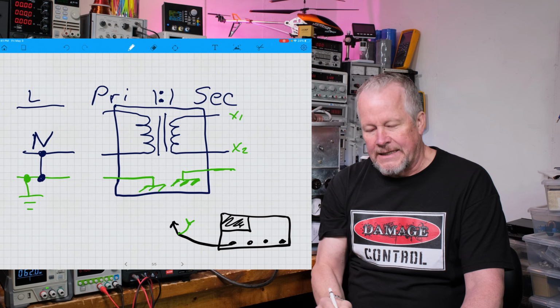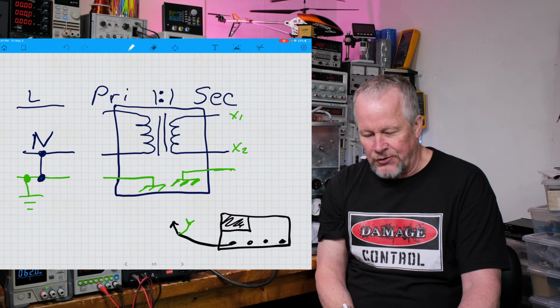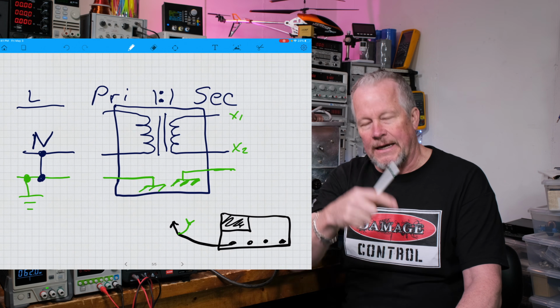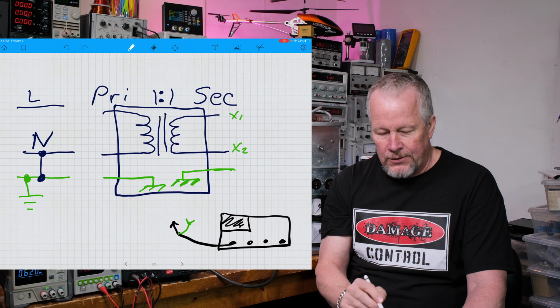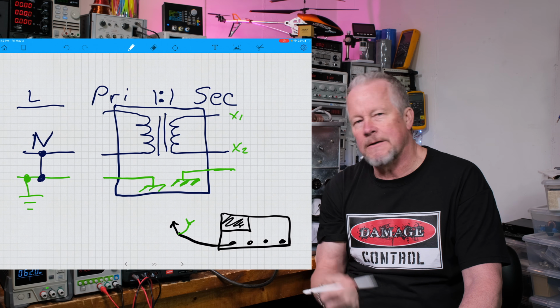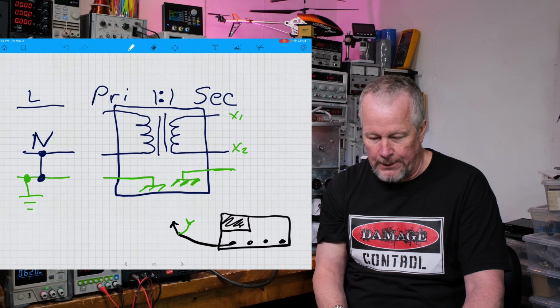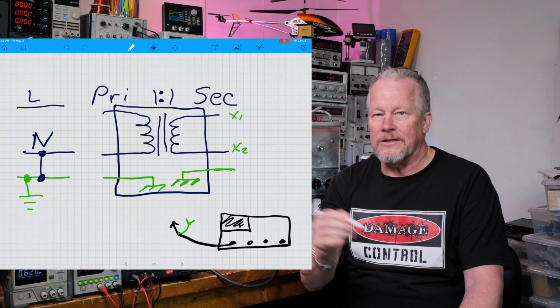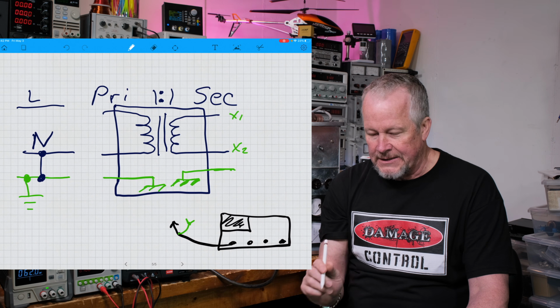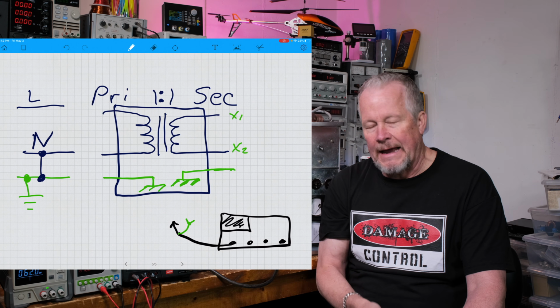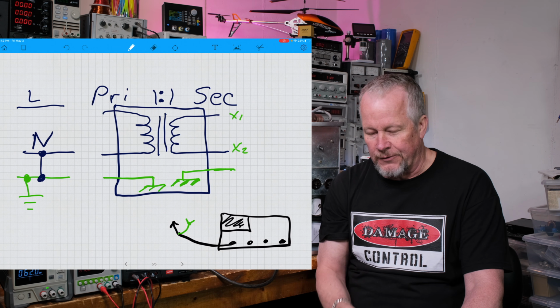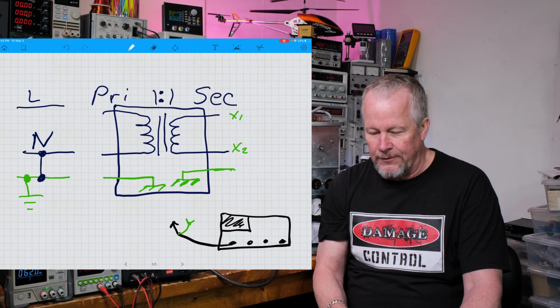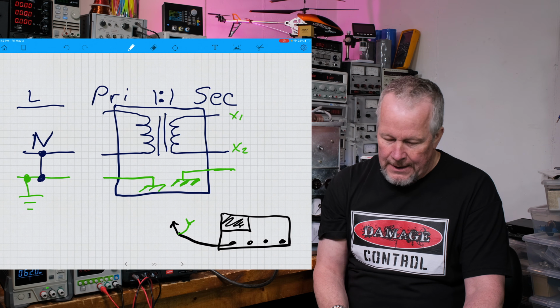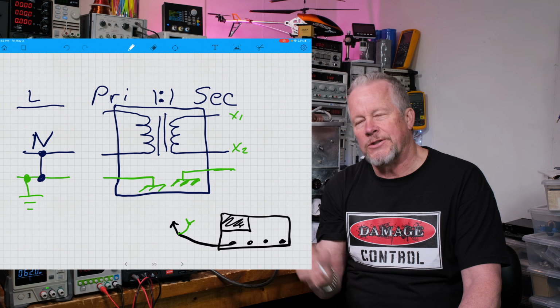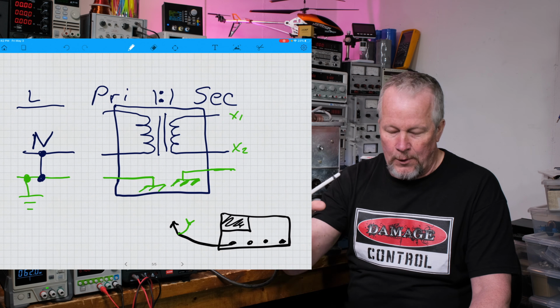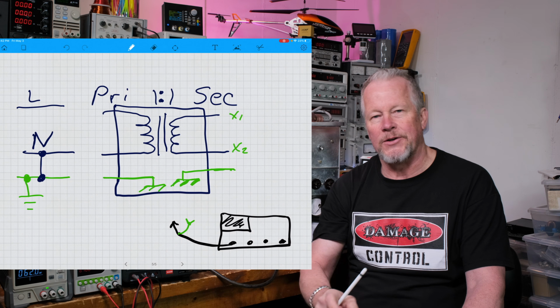So in this case, on this isolation transformer, let's go to the primary side. If I touch that green one to neutral or to chassis, it's fine, because that's the same connection point. But if I tie it to line, I just shorted those, that's bad. On the secondary side, if I had that bond, I'd have the same situation. But since I don't have that bond to chassis with my winding, it's floating. Now I can touch that to either X1 or X2, it doesn't matter. It's just floating. Now I've referenced it to my chassis by doing that.